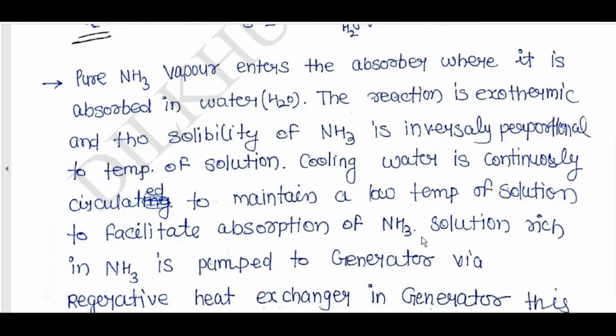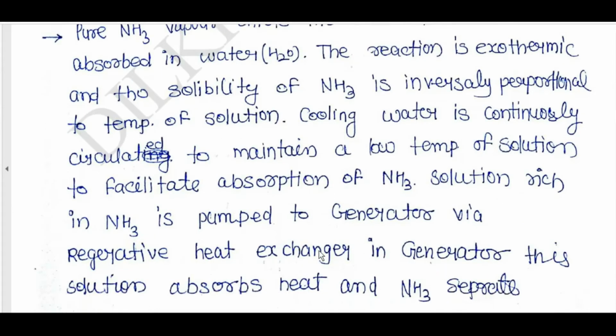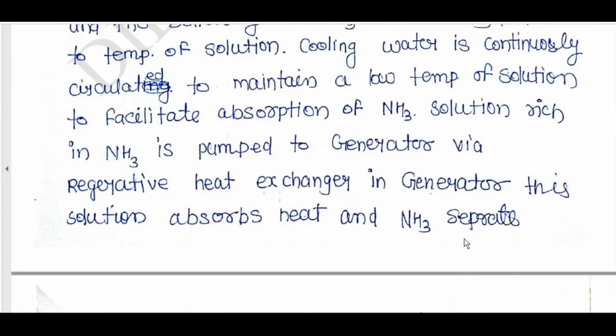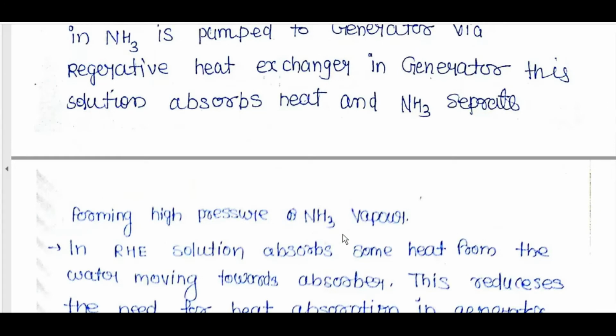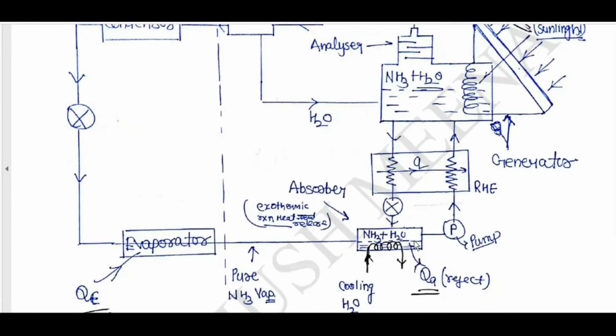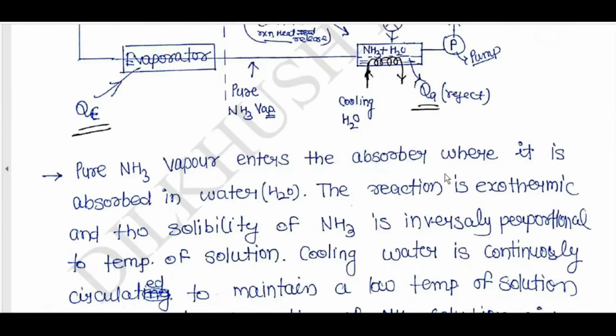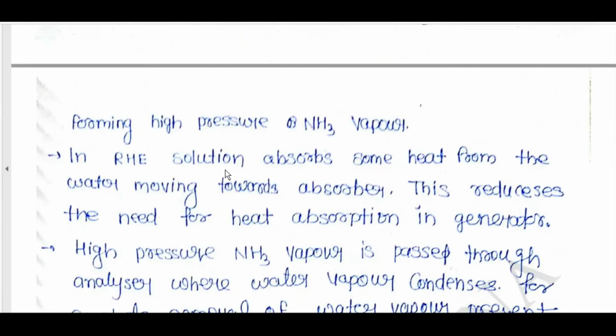To facilitate absorption of NH3, the solution rich in NH3 is pumped into the generator via a regenerative heat exchanger. In the generator, this solution absorbs heat and NH3 separates as high pressure NH3 vapor. Here it will pass through the pump, then the regenerative heat exchanger. In the regenerative heat exchanger, the solution absorbs some heat from the water moving towards the absorber. This reduces the need of heat absorption from the generator.